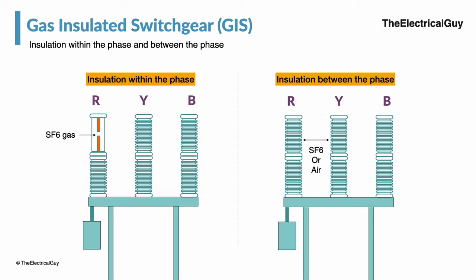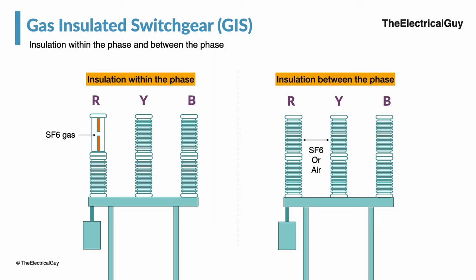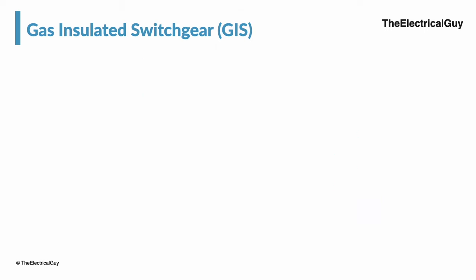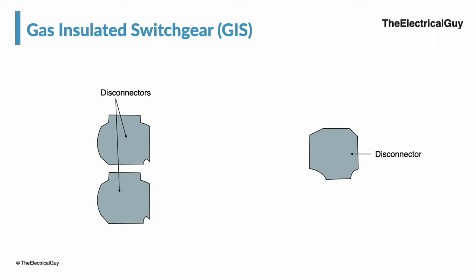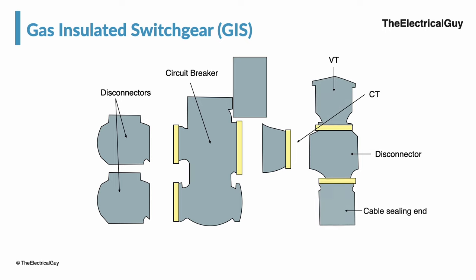On the other hand, in AIS technology only insulation within the phase is provided by SF6 gas, and insulation between the phases is air — hence the name air insulated switchgear. In GIS technology all the switchgear, like disconnector and earthing switch, circuit breaker, current transformer, and voltage transformer, are insulated by SF6 gas. Not only this, even the bus bars are also insulated by SF6 gas.